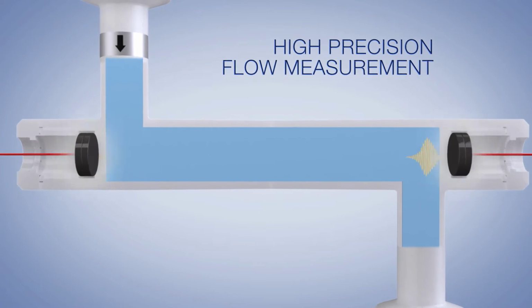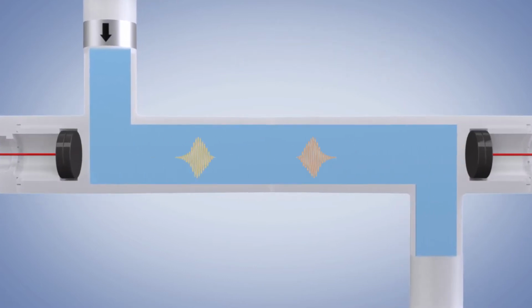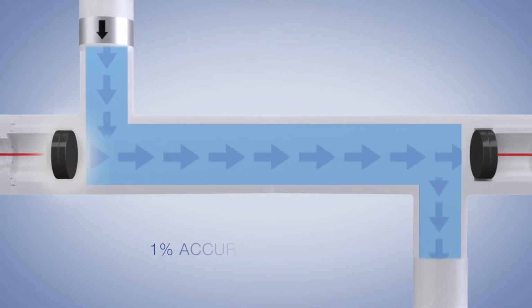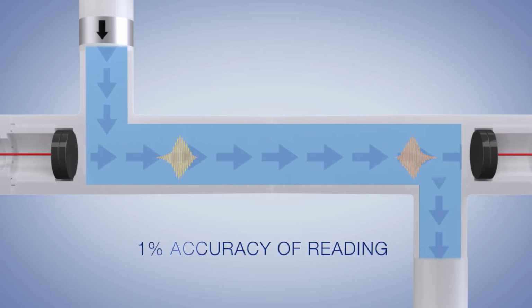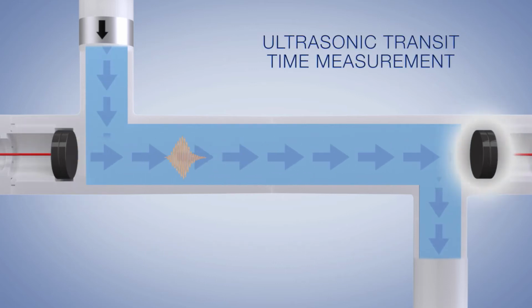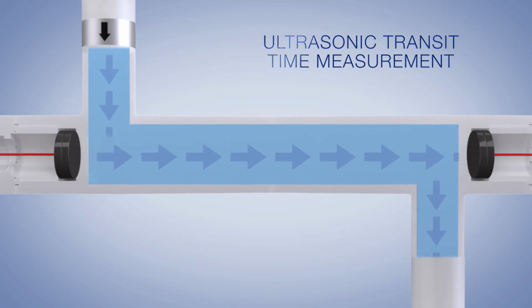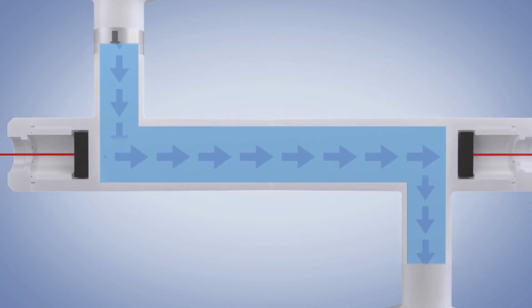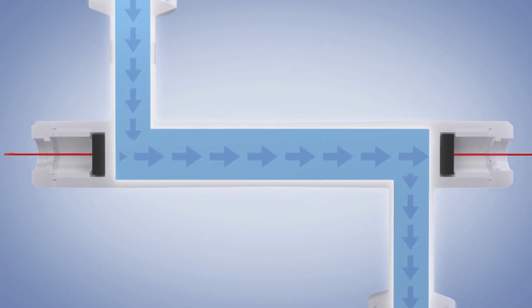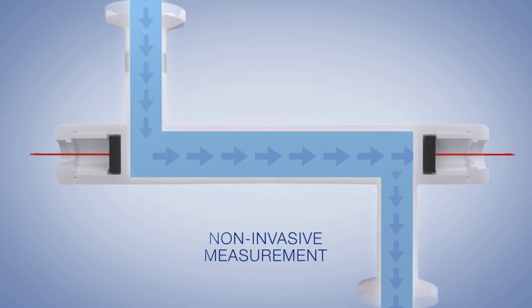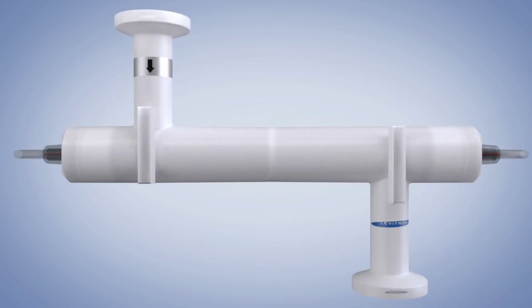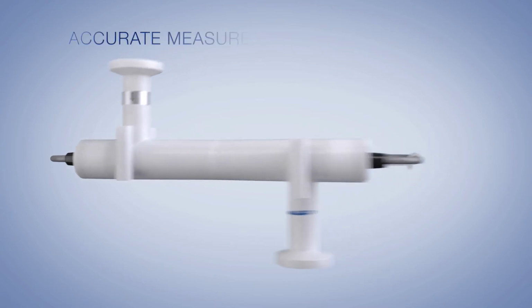Two piezoelectric transducers generate and receive ultrasonic waves. When flow is present, the with-stream wave is accelerated, and the against-stream wave is slowed down. The difference in transit time is proportional to the velocity of the fluid. The measurement is completely non-invasive and robust against high pressures.